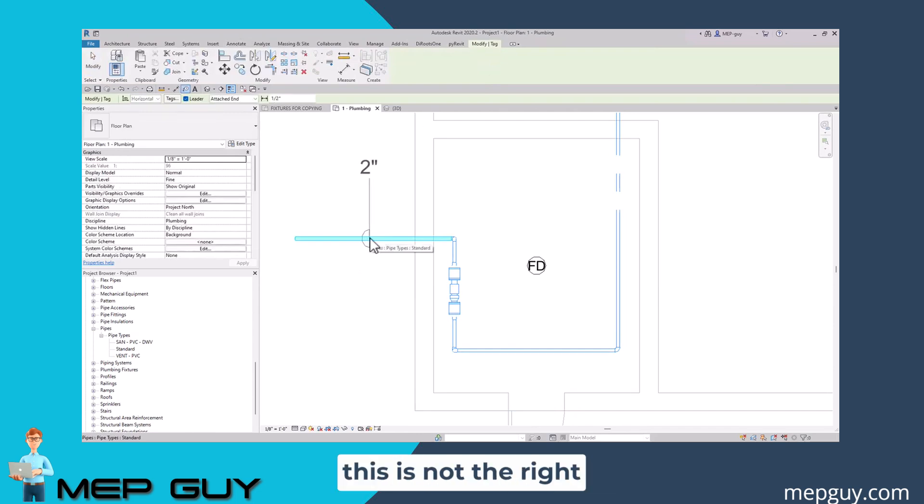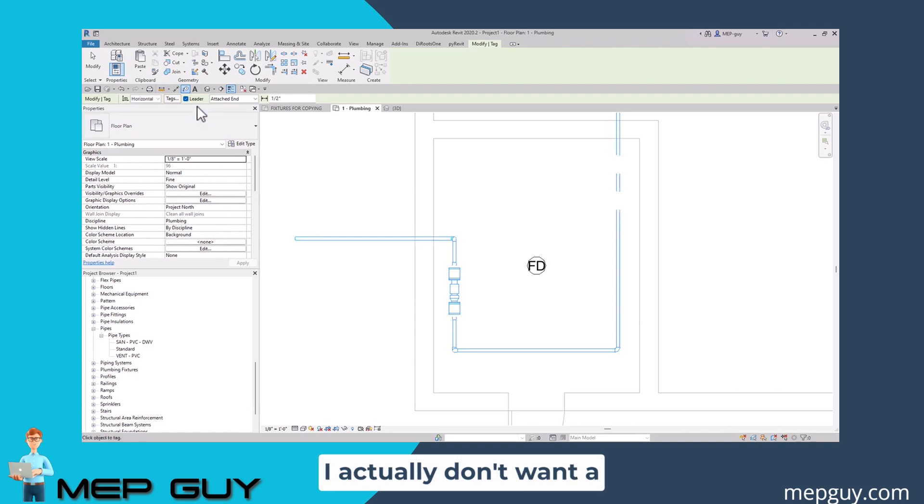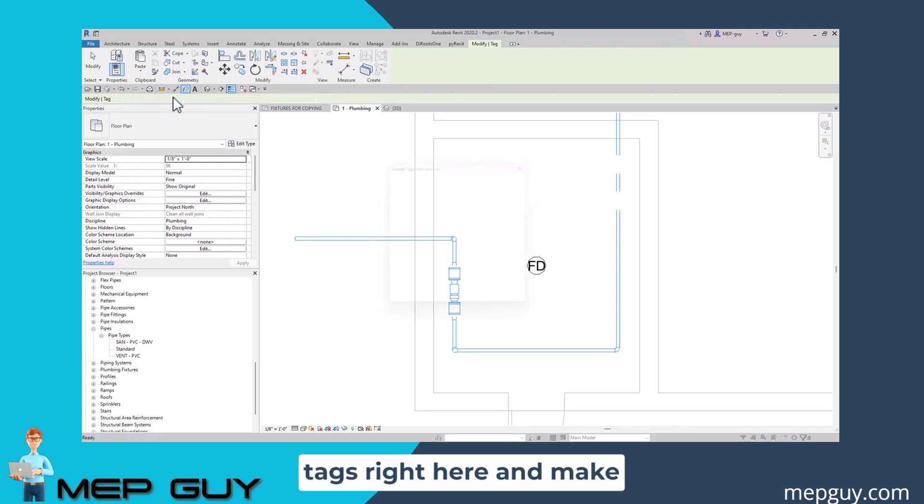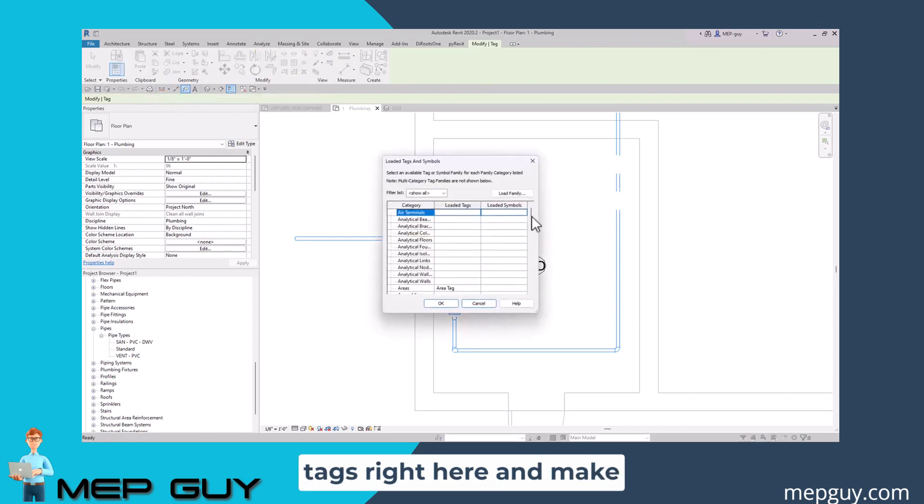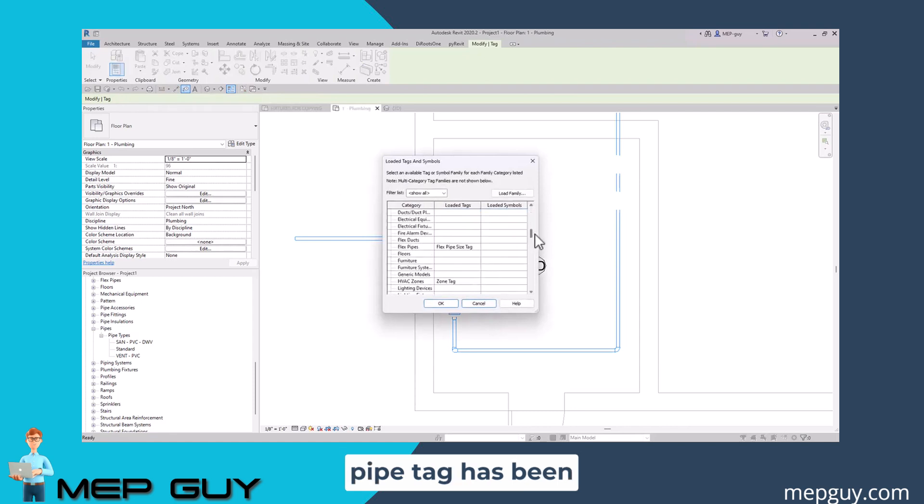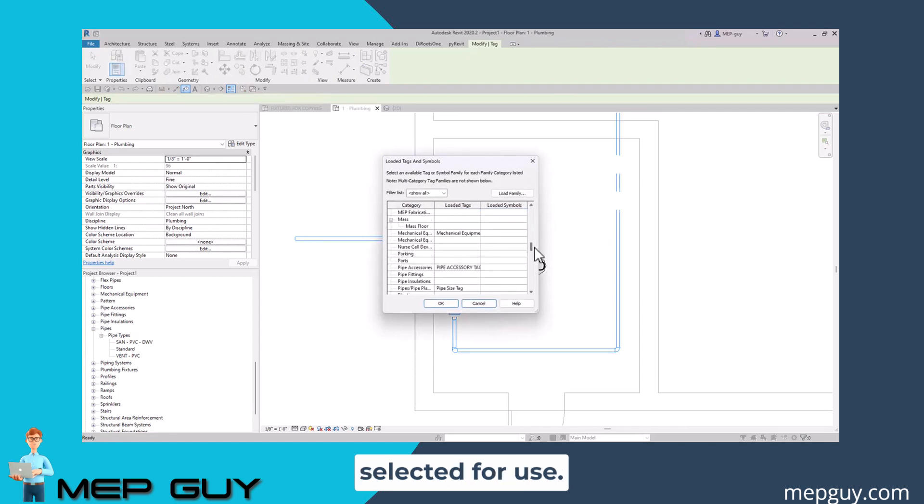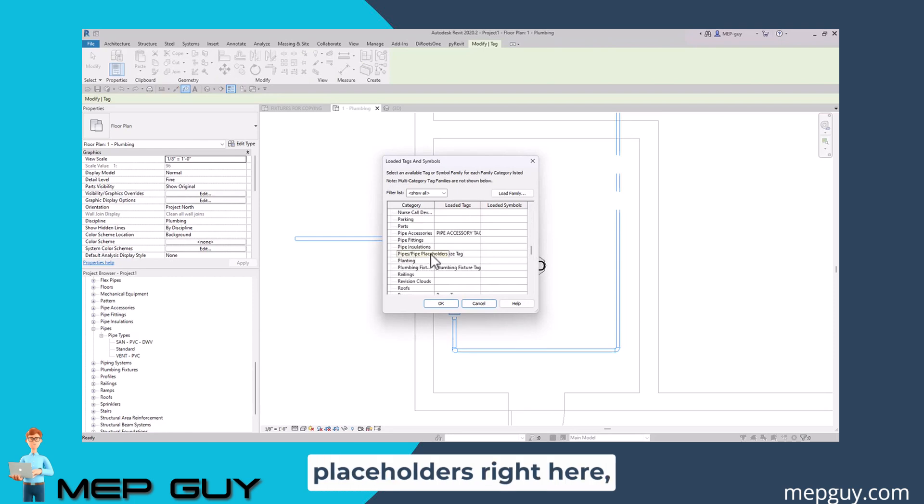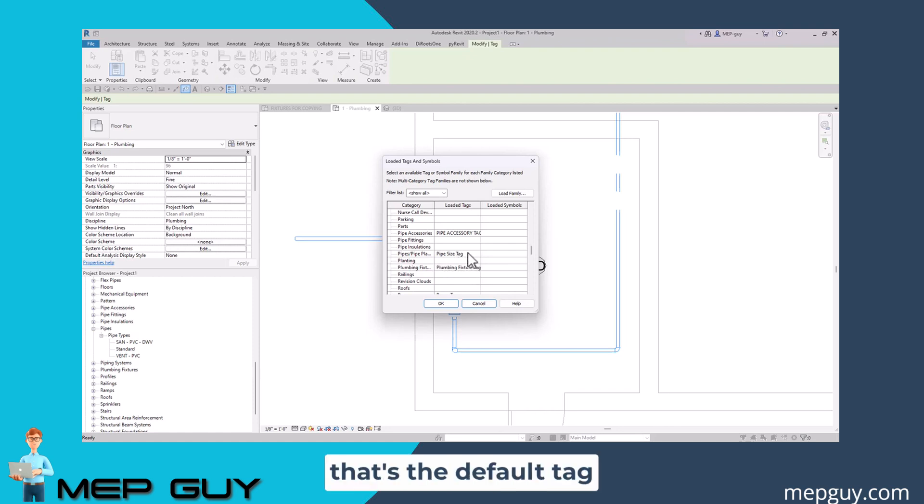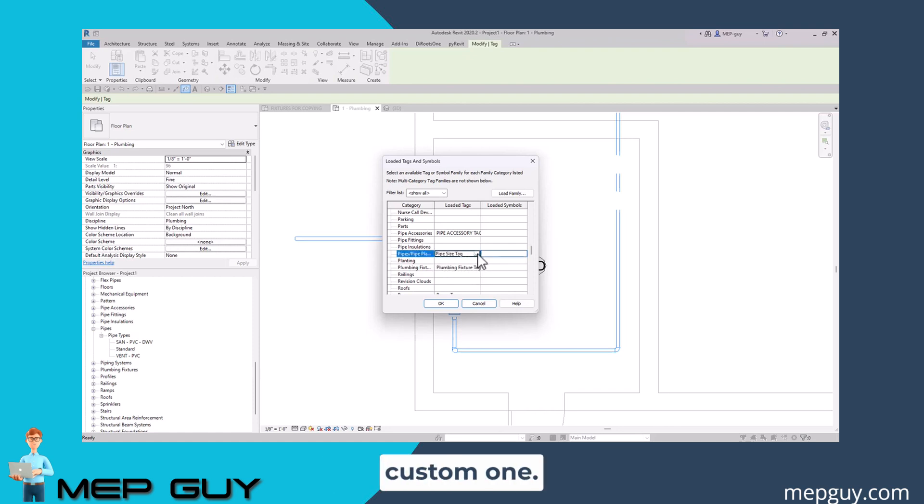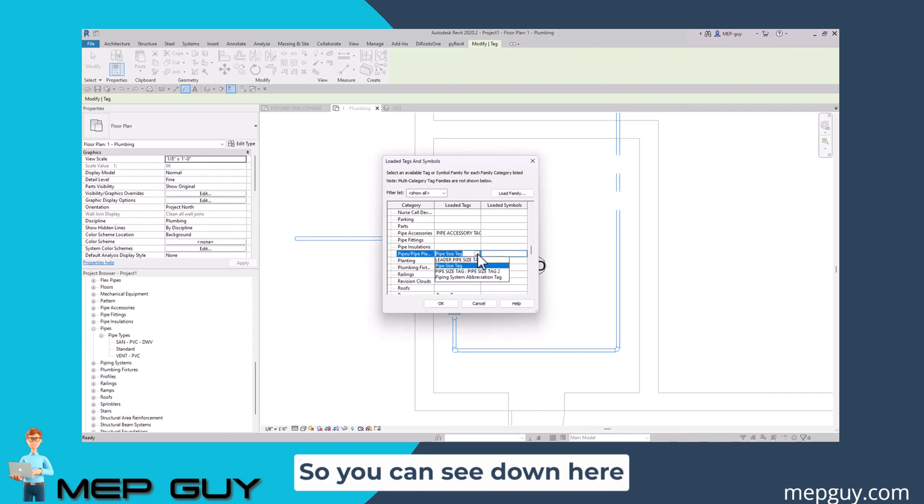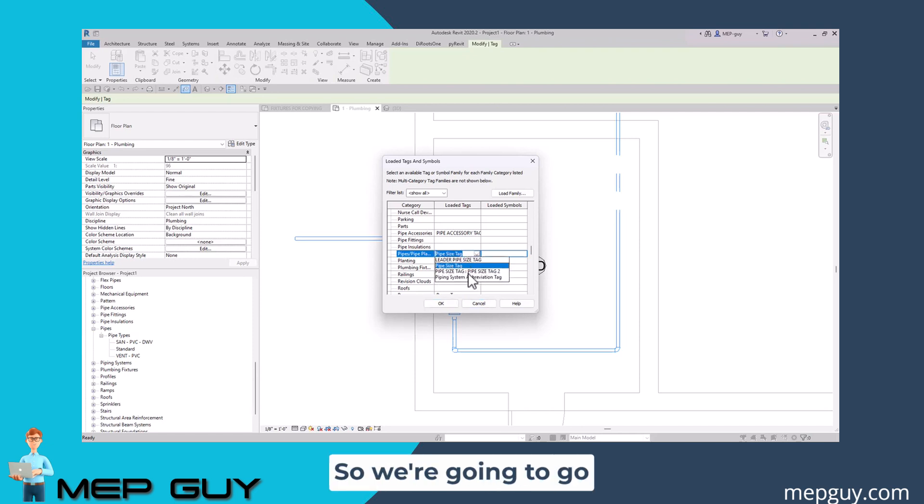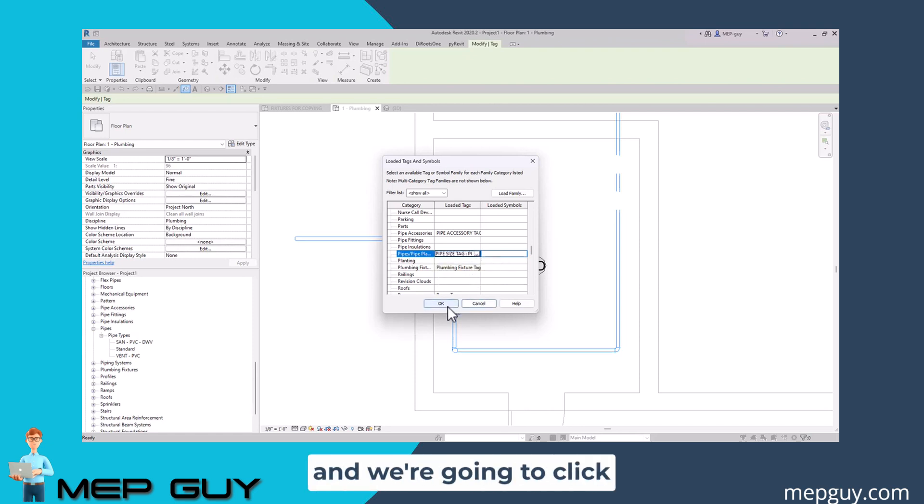This is not the right tag I want to use. I actually don't want a leader and I want it to display that abbreviation. I need to go into my tags right here and make sure that the correct pipe tag has been selected for use. If you see right down here, pipes and pipe placeholders, we're using this pipe size tag. That's the default tag that Revit has, but I want to use my custom one. You can see down here, I have two custom pipe tags, one that says pipe size tag in all caps. We're going to click this one and click okay.